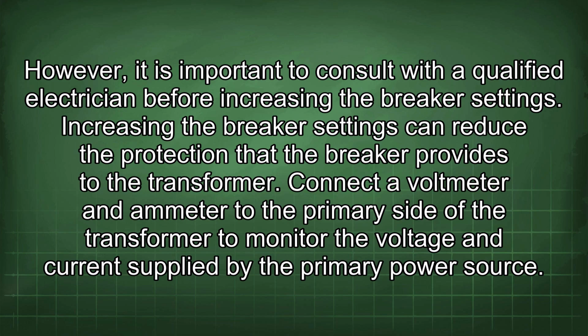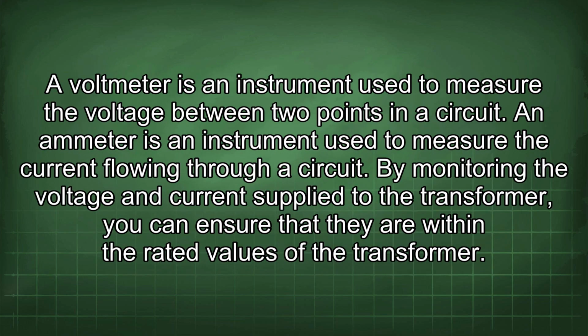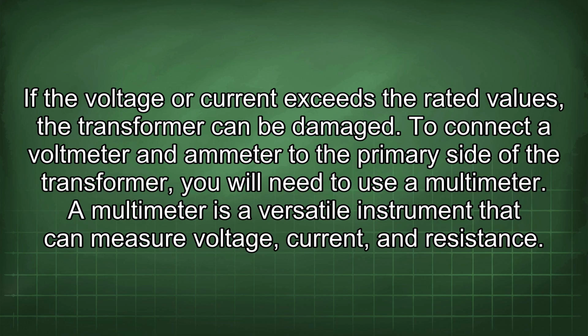Connect a voltmeter and ammeter to the primary side of the transformer to monitor the voltage and current supplied by the primary power source. A voltmeter is an instrument used to measure the voltage between 2 points in a circuit. An ammeter is an instrument used to measure the current flowing through a circuit. By monitoring the voltage and current supplied to the transformer, you can ensure that they are within the rated values of the transformer. If the voltage or current exceeds the rated values, the transformer can be damaged. To connect a voltmeter and ammeter to the primary side of the transformer, you will need to use a multimeter. A multimeter is a versatile instrument that can measure voltage, current, and resistance.